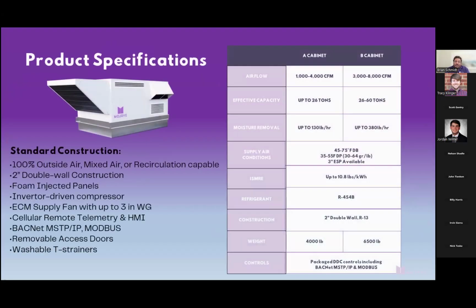Some of the specifications really quick. As I mentioned in the beginning of this presentation, I'm not getting too heavy into the specs or the customizable features. It was really meant more to show you the technology and how it's applied. Our standard construction, again, is 100% outside air, or mixed or recirc capable, 2-inch double wall construction, foam injected panels, inverter driven compressor, and ECM supply fan. We do have that remote telemetry I mentioned before on every single unit.